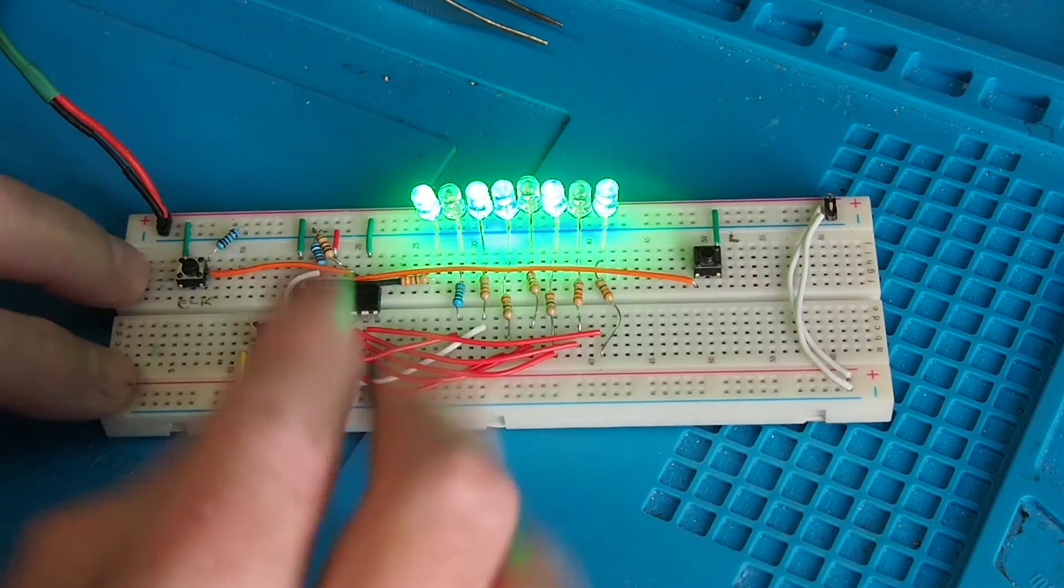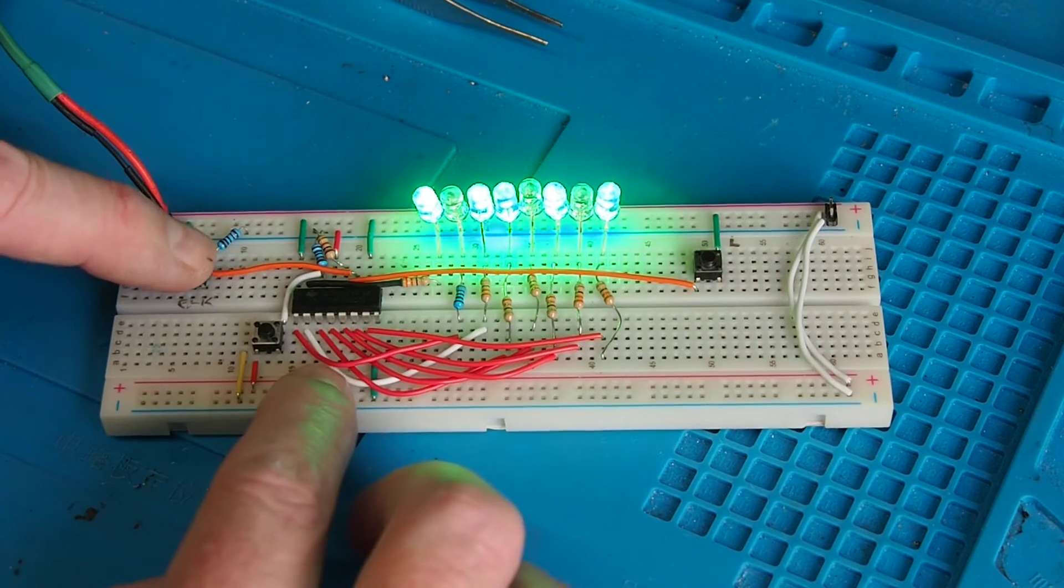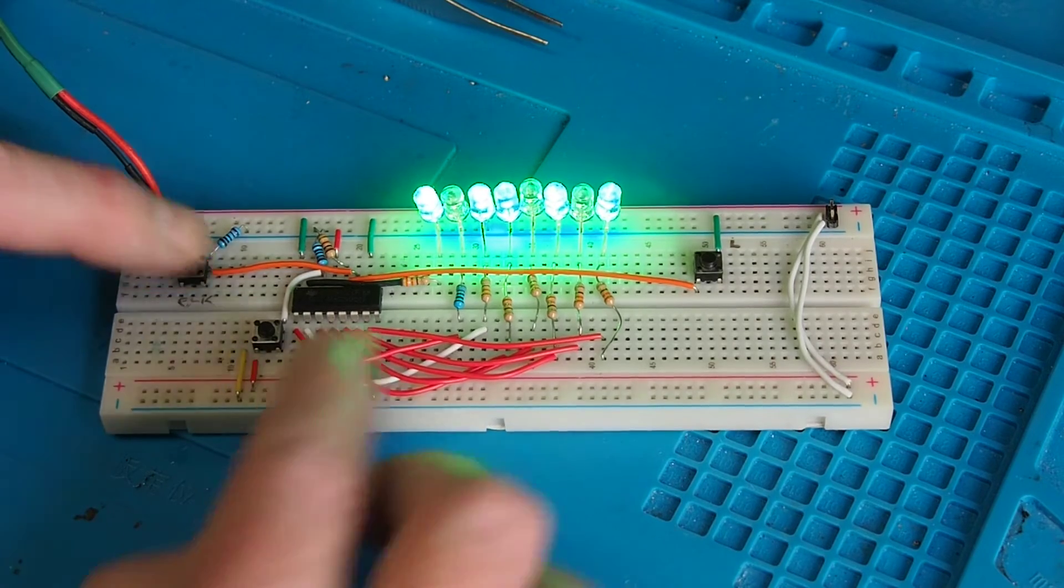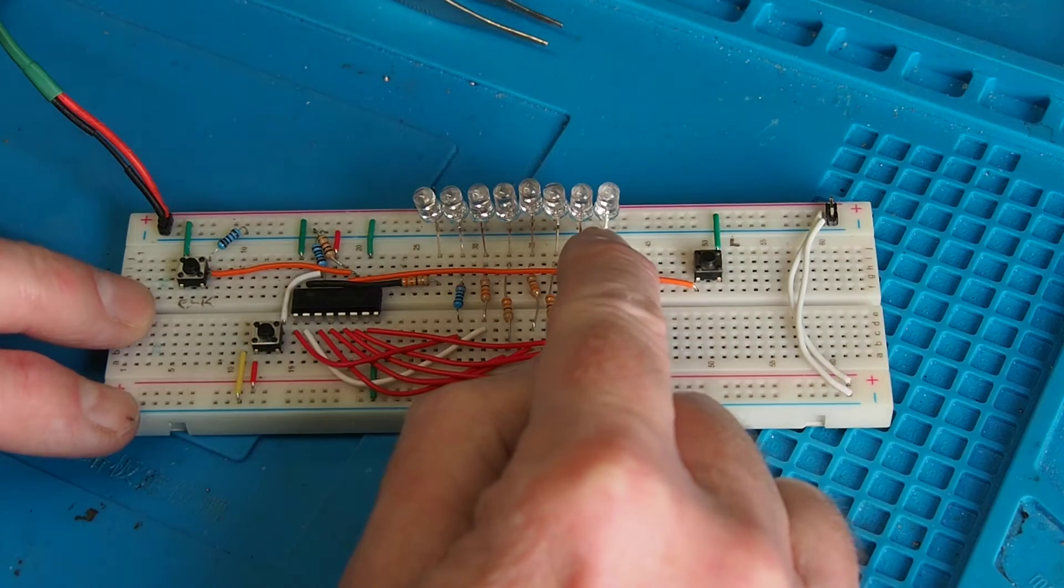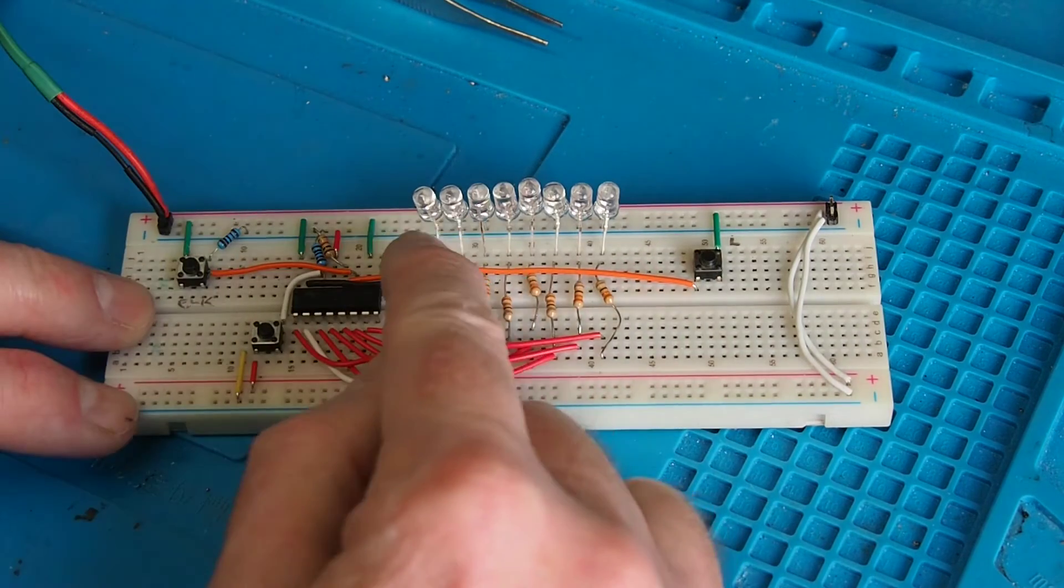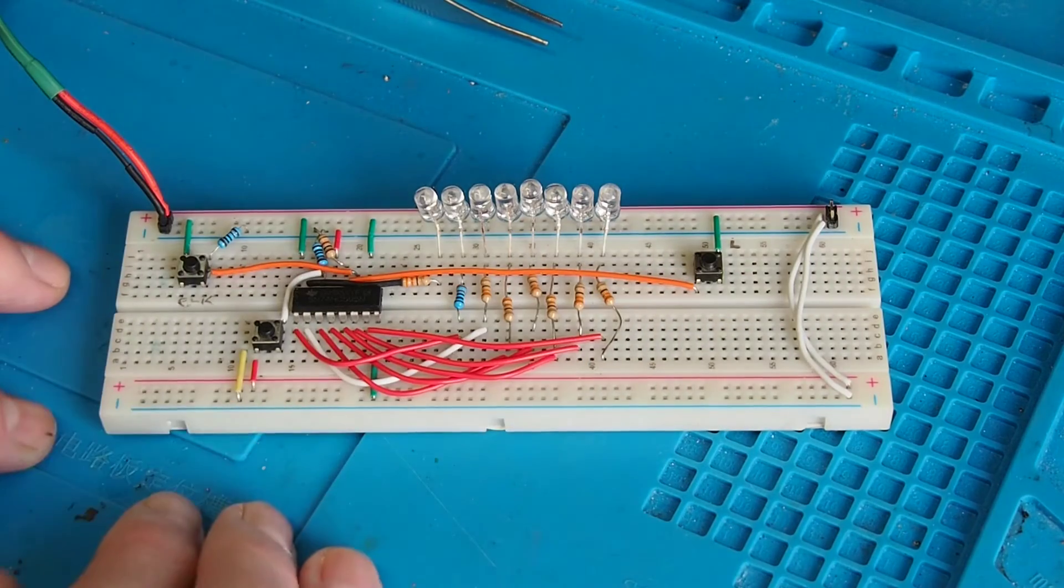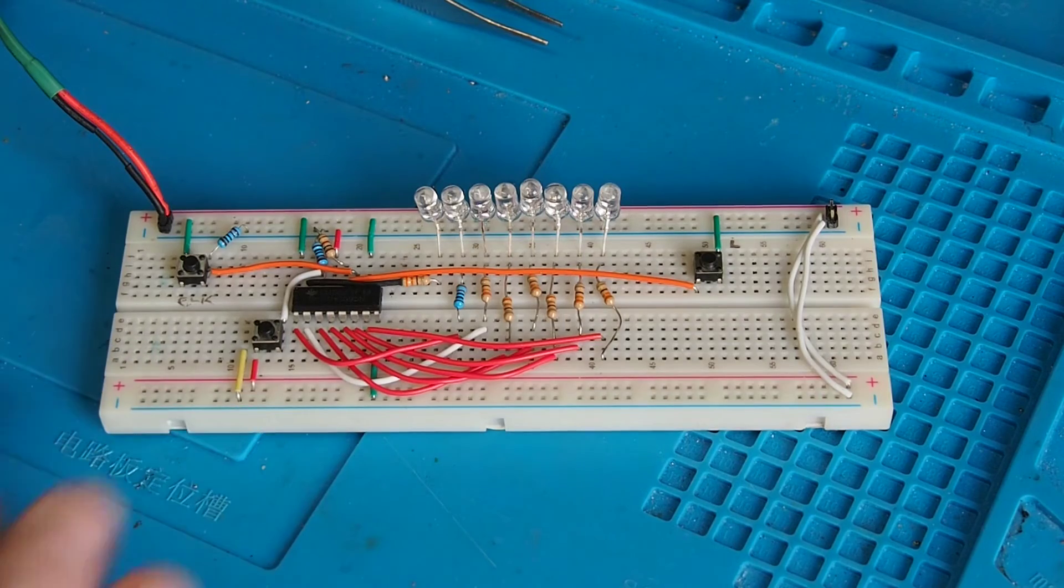One, two, three, four, five, six should clear everything to there, and it's actually emptied it. I only pressed it six times, it's actually got more than eight pulses to empty that. So rather luckily for me whilst filming this, that's the fault which I needed to correct.